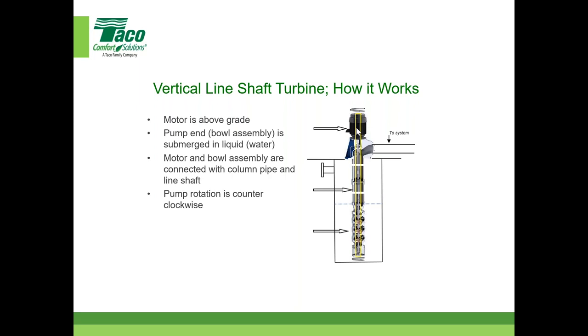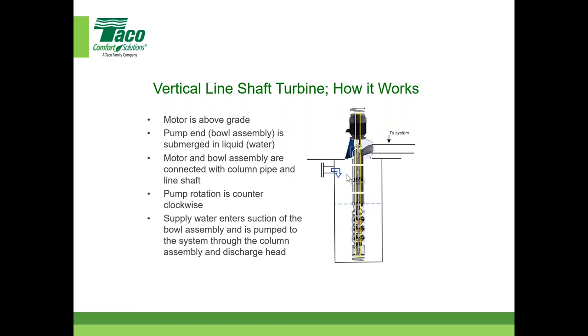And then the pump rotation. There's a column here that attaches the bowl assemblies, very important. You can see the water comes in into the bottom here, goes up the line shaft and then out to the system. So pretty straightforward, but that's how it works nonetheless.